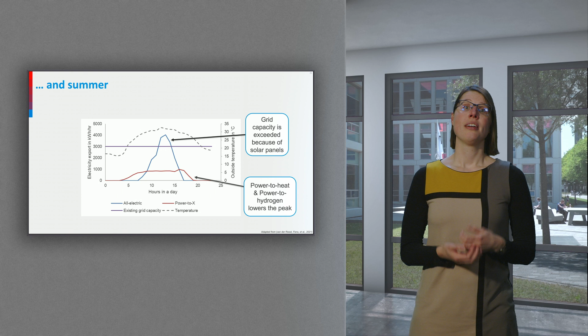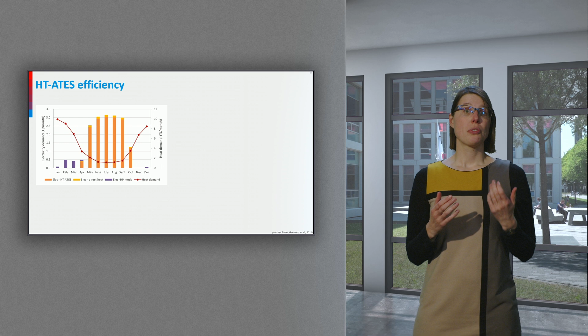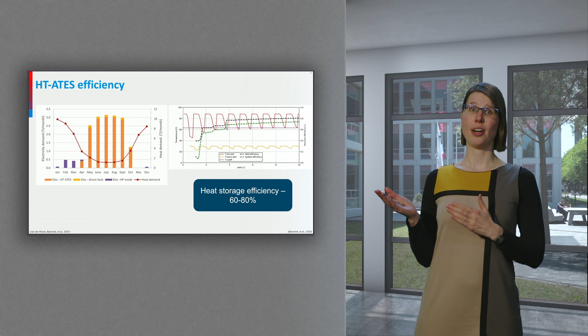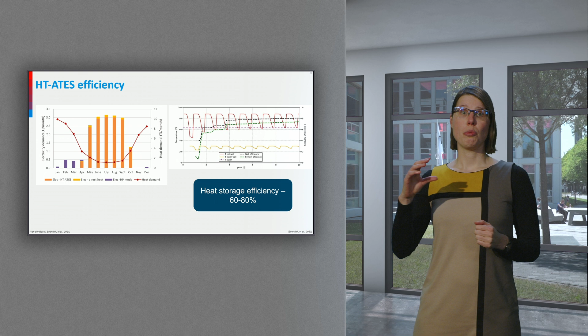How does the high temperature ATES system function? The graph clearly shows how heat demand and heat supply are decoupled over time. In terms of storage efficiency, 60 to 80% efficiency can be reached depending on, for example, the heat storage temperature. Here an example is shown of a very high storage temperature of 90 degrees Celsius. Over time, you see that the system will get more efficient, just as low temperature ATES systems.